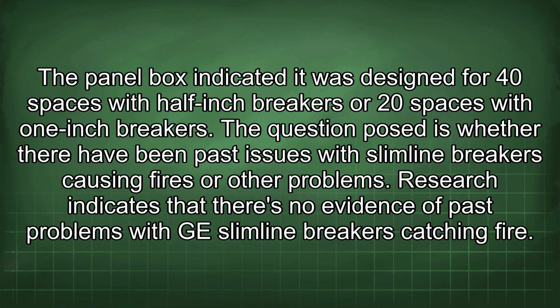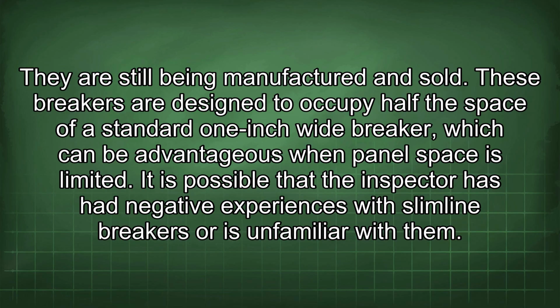The panel box indicated it was designed for 40 spaces with half-inch breakers or 20 spaces with 1-inch breakers. The question posed is whether there have been past issues with slimline breakers causing fires or other problems. Research indicates that there's no evidence of past problems with GE Slimline breakers catching fire. They are still being manufactured and sold.